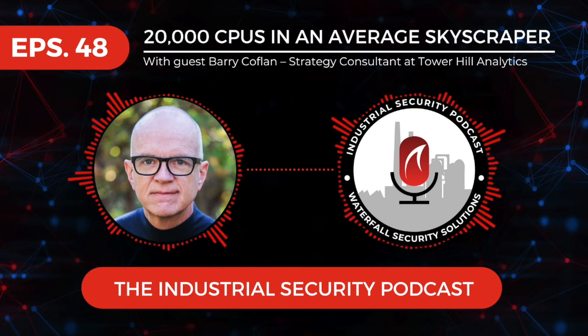For older buildings, for older systems, what are the options there? How do you protect them? It's tough. It's really tough. So realize that when we mention that number of controllers, 20, 30,000 controllers in some cases, these controllers are built into walls. They're plastered in some cases. It's not like a removable ceiling. They're very, very difficult to remove and upgrade. And the life cycle of a building management system can be 20, 30, 40 years even. So trying to rip and replace and put in a new modern system is not trivial.